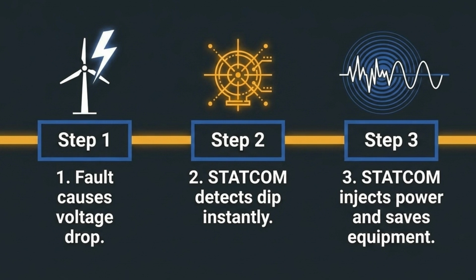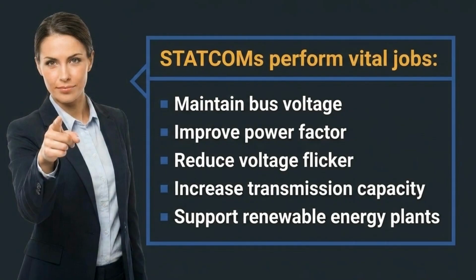STATCOMs are fast-acting. For example, if a fault causes a voltage drop, the STATCOM detects this dip instantly and injects power to protect equipment. STATCOMs perform vital jobs, including maintaining bus voltage, improving the power factor, reducing voltage flicker, and supporting renewable energy plants.